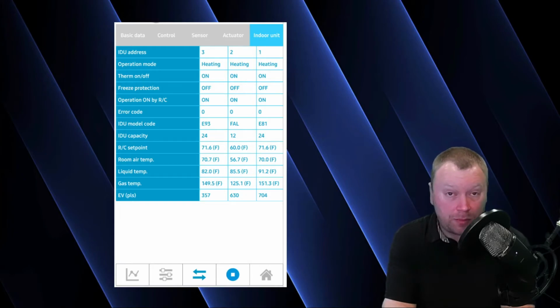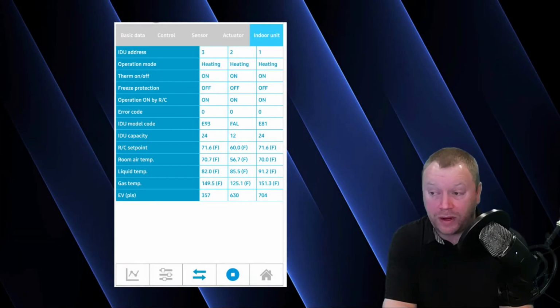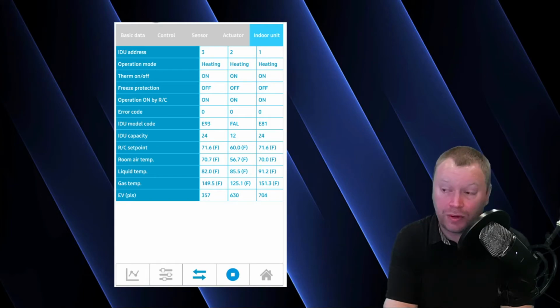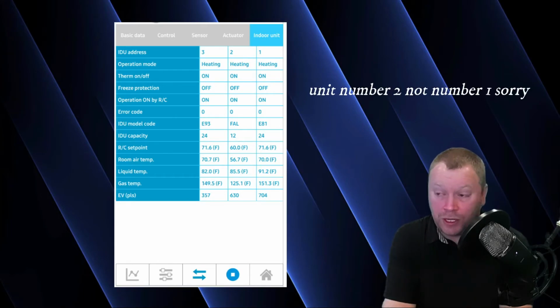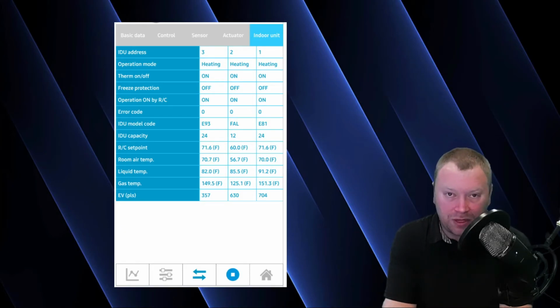But look at our set points versus room temps. RC set point 71.6 degrees versus room air temperature of 70.7. So we're very close to our set point here on unit number 3. Unit number 2 is in my garage. My garage is cold. It's definitely calling for a little bit more. So I'd like to see unit number 2 start to perform a little bit better. Again, we're only 9 to 10 minutes into this recording at the time of the snapshot. So over the next 10 minutes, that gas temperature is going to come up. Our liquid temperatures are also going to come up. And that's what I would expect to see over the next several minutes.